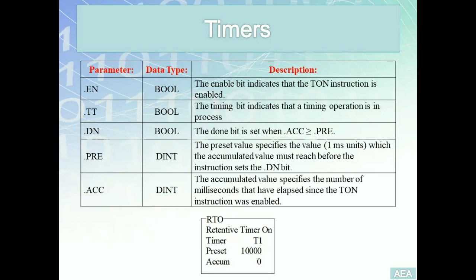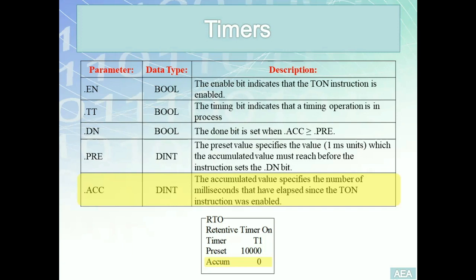The preset parameter requires no complex analysis. Since the base unit in Allen Bradley is a millisecond, if you want the timer to run for one second, the preset value must be 1,000. For 10 seconds, that's 10,000. The accumulator is another double integer that tells us how long the timer has been active. If the preset is 10,000 milliseconds, the accumulator will count from zero up through one second, two seconds, three seconds, up to 10 seconds.